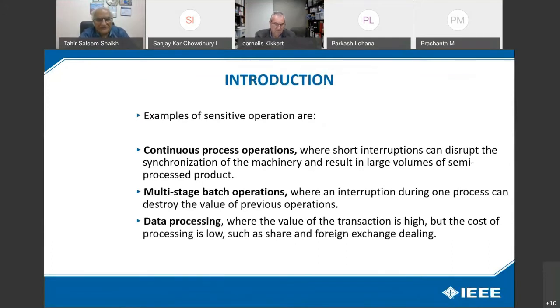A few examples of sensitive operations are continuous process operation. If I have a plant which has continuous operation, a slight sag or dip will disturb the whole plant. Multi-stage batch operation, where interruption during one process can destroy the value of a previous operation, and the whole plant may stop. Data processing, where the value of the transaction is high but the cost of the processing is low, such as share and foreign exchange dealings.